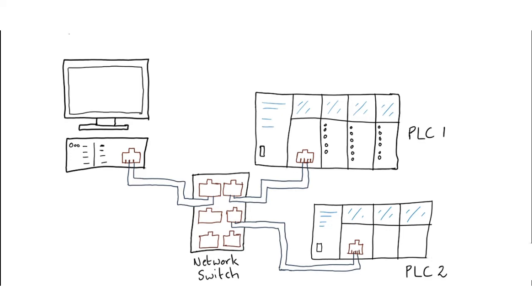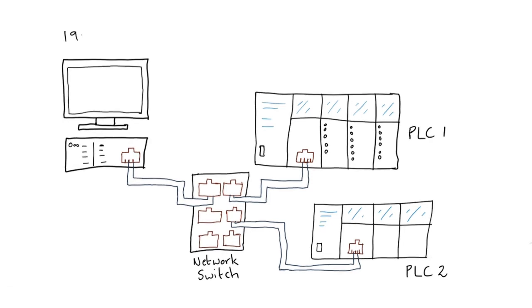However, here is the catch: when you connect your engineering workstation to the PLC, they don't immediately pick each other up. So the communication path is not easily set up as in a USB connection. In order for the tool to communicate, you need to know the IP address of the PLC. Then you need to change the IP address of your engineering workstation to be on the same network range as the PLC's IP address.